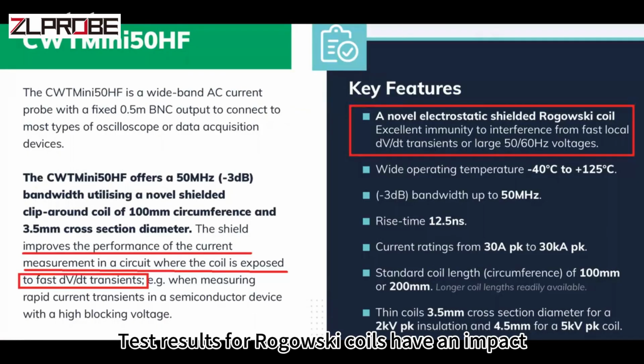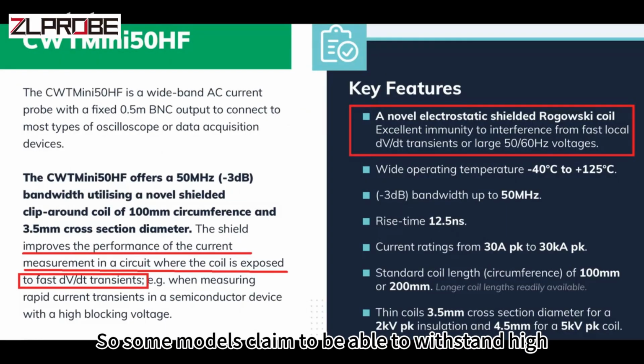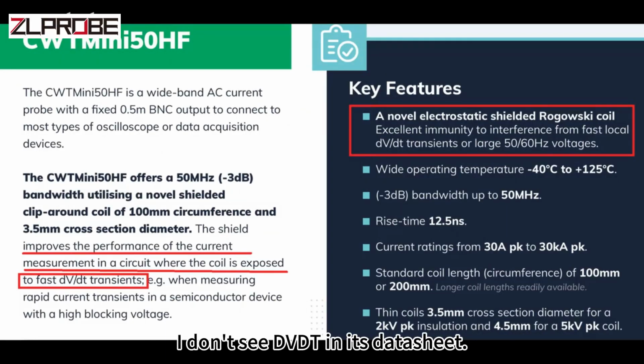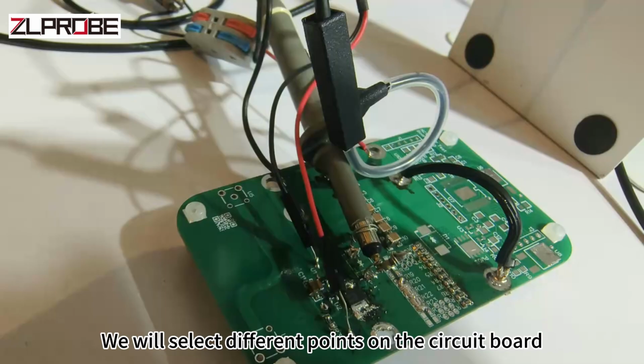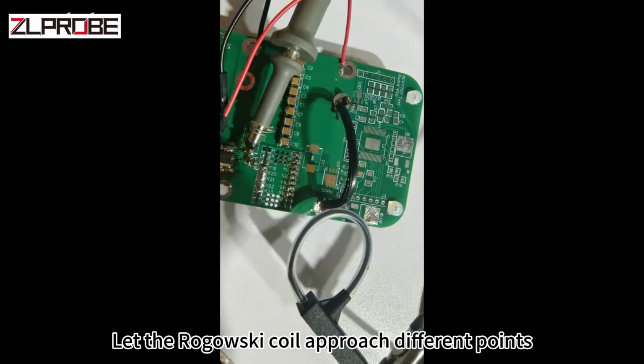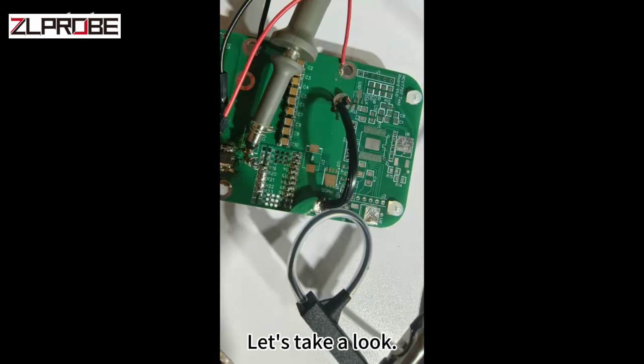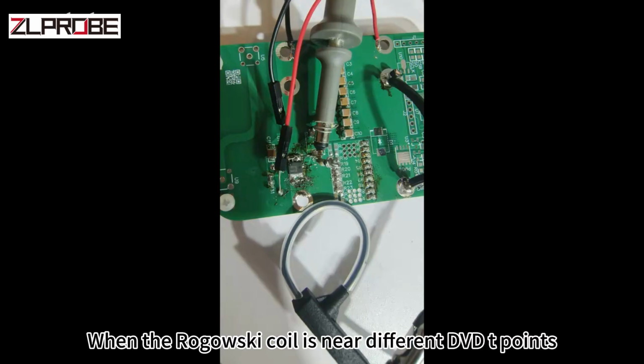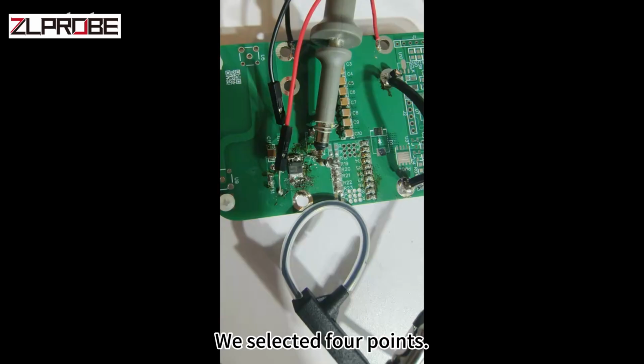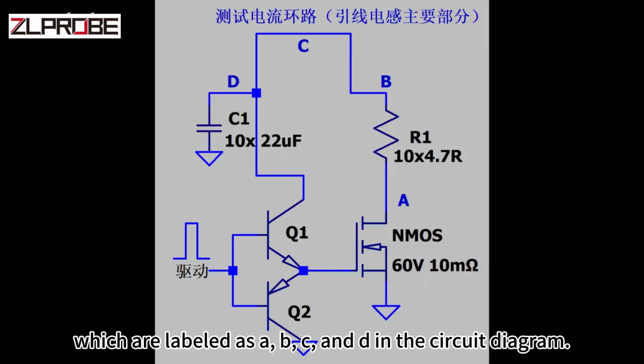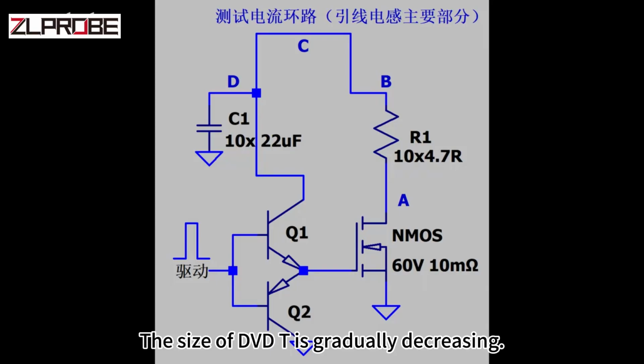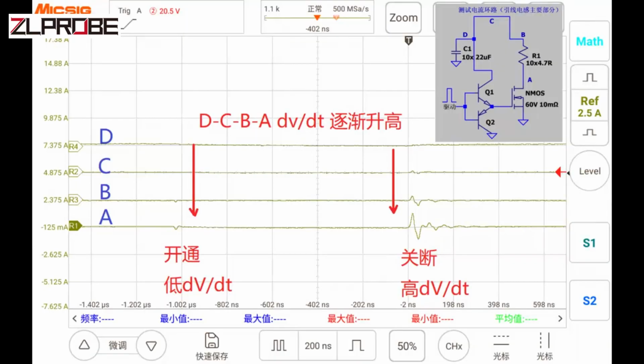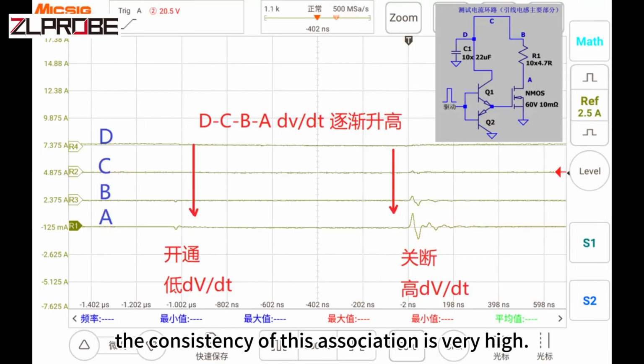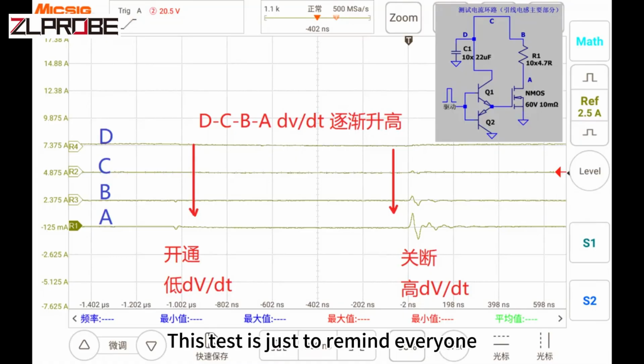High dV/dt may have an impact on Rogowski coils, so some models claim to be able to withstand high dV/dt. I don't see dV/dt in its datasheet. To see the relevant parameters, we will select different points on the circuit board. Let the Rogowski coil approach different points. These points have different dV/dt's. Let's take a look. When the Rogowski coil is near different dV/dt points, what kind of change will its output have? We selected 4 points, which are labeled as A, B, C, and D in the circuit diagram. The size of dV/dt is gradually decreasing. The result shows that the consistency is very high. This test is just to remind everyone to pay attention to the impact of dV/dt.